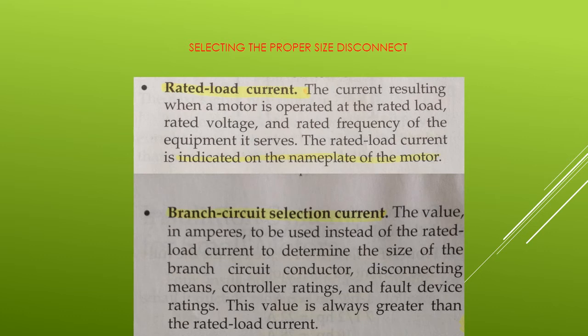The second term is branch circuit selection current. This is the value in amperes to be used instead of the rated load current to determine the size of the branch circuit conductor, disconnecting means, controller ratings, and fault device ratings. This value is always greater than the rated load current. The disconnecting means rating for a hermetic motor shall be 115% of the nameplate rated load current, or the branch circuit selection current, whichever is greater. The equivalent horsepower is determined in the same way as described earlier for determining controller horsepower. Again, the larger value is the one used to select the proper disconnect.